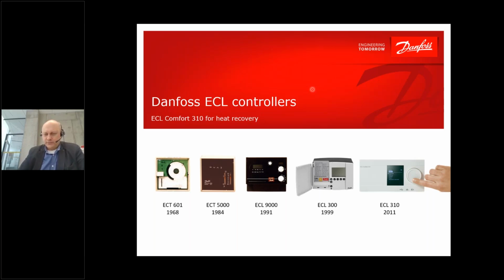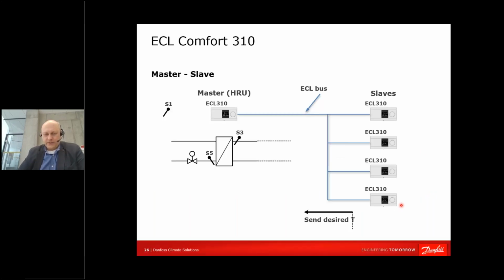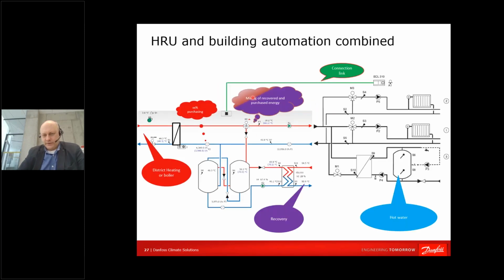With this slide, I would like to show you the ECL 310 controller, which we're using now and which is capable of running a specific heat recovery program. We are utilizing a combined master and slave solution, so slaves in the building might ask the master to deliver the temperature they want. And it looks like that. We are recovering energy to the tanks, sending energy to the three-way valve, and sending energy to the building.